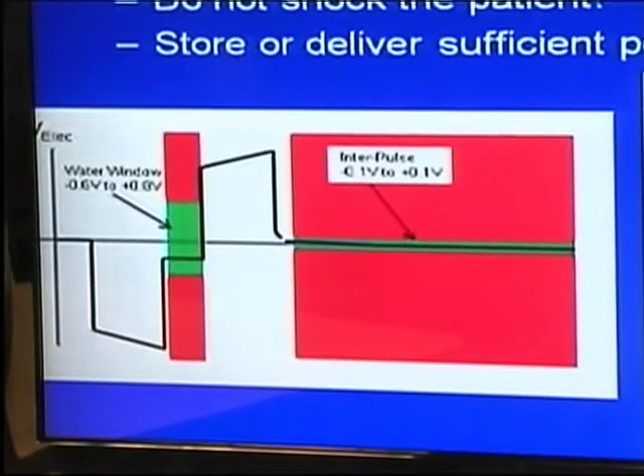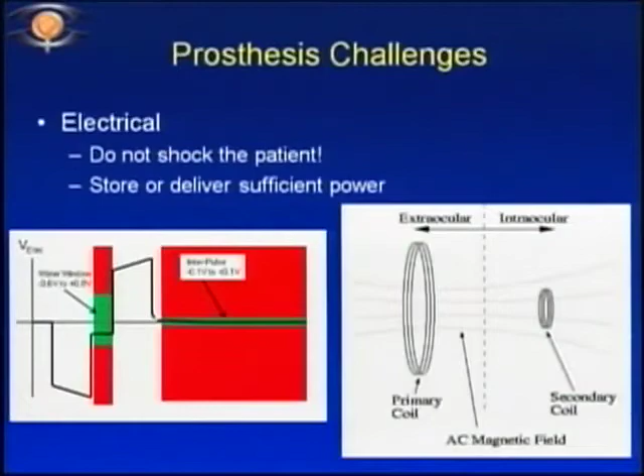So here on the left, we look at the voltage across an electrode. And there are a couple of places during that stimulation, a couple of times when we want to very carefully monitor that voltage and use our safety features to detect whether that electrode is still operating in its safe region. And if it's not, there are other safety features that will either correct for that or take that electrode out of the picture. And in a retinal implant with hundreds of electrodes, you can afford to have an electrode fail and just be removed from operation.